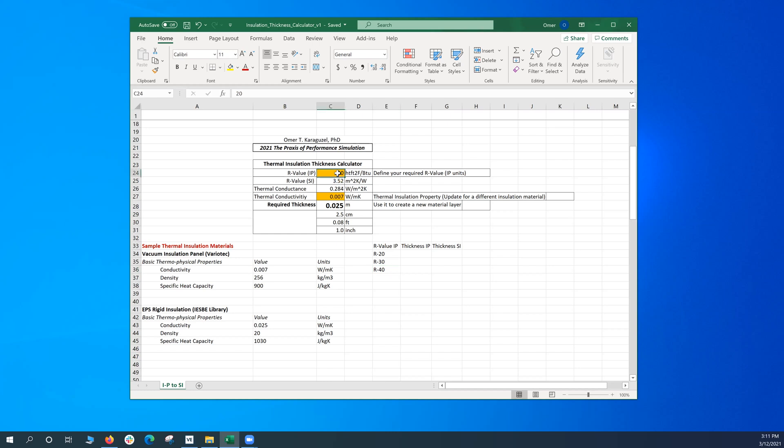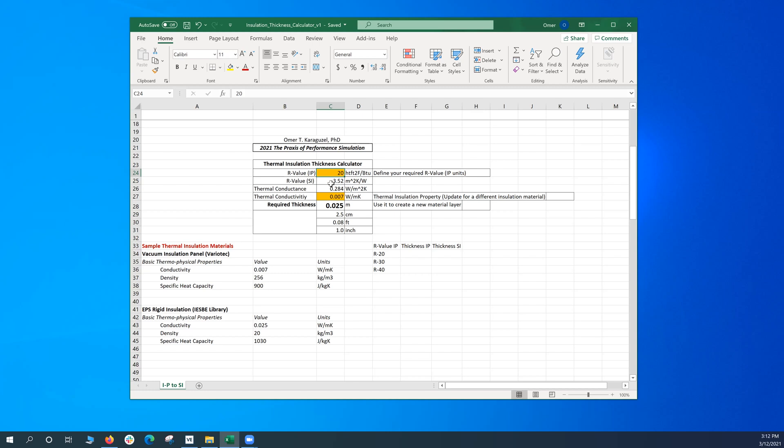So this calculator takes this target value and based on a specific thermal insulation material, calculates the required thickness. The calculator also has another function of conversion from IP to SI system, because these R-value discussions are mostly done in the IP system, but you can convert it to the R-value in the SI system, then reverse it, take the reciprocal and calculate thermal conductance and also the thickness. The thickness data is also given as meters, centimeters, feet, and inches.